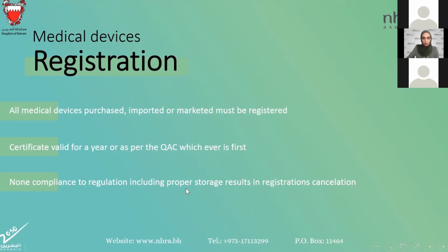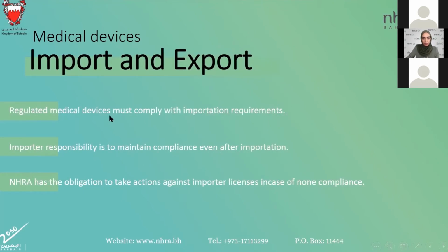Non-compliance to regulation, including proper storage, results in registration cancellation. Import and export: every medical device regulated, as in the HS code is regulated, must comply with importation requirements. Importer is responsible to maintain the compliance even after importation. So if the device was imported and we've discovered that it was not transported, was not stored in a proper manner as per the manufacturer requirements, the responsibility will fall under the importer himself.